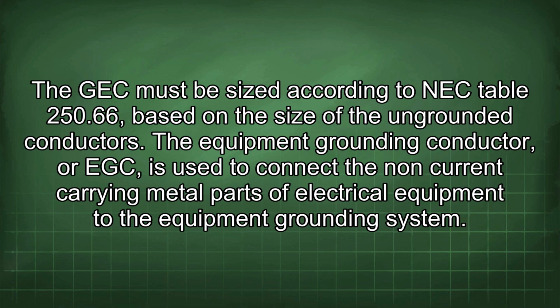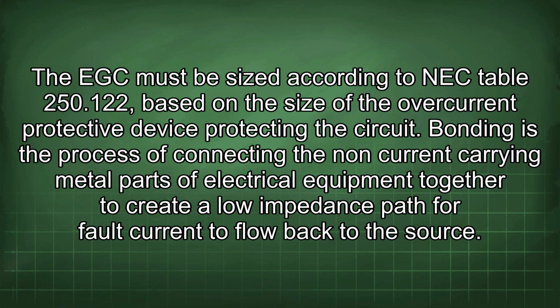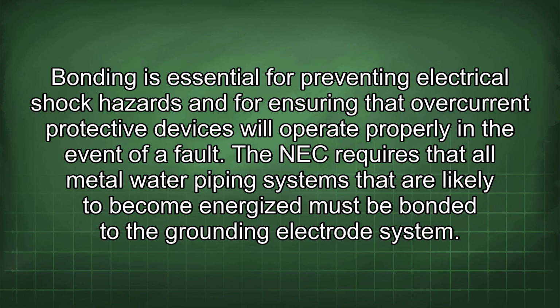The equipment grounding conductor, or EGC, is used to connect the non-current carrying metal parts of electrical equipment to the equipment grounding system. The EGC must be sized according to NEC Table 250.122, based on the size of the overcurrent protective device protecting the circuit. Bonding is the process of connecting the non-current carrying metal parts of electrical equipment together to create a low impedance path for fault current to flow back to the source. Bonding is essential for preventing electrical shock hazards and for ensuring that overcurrent protective devices will operate properly in the event of a fault.